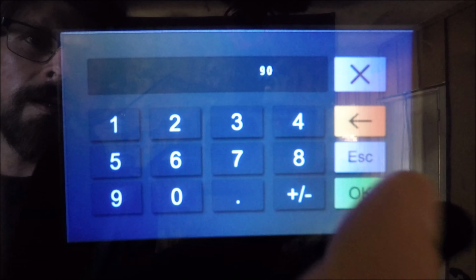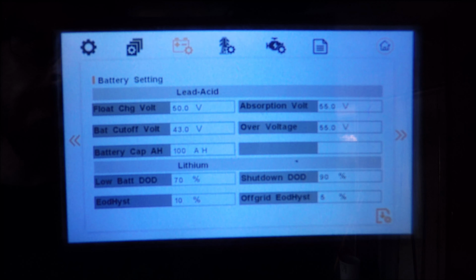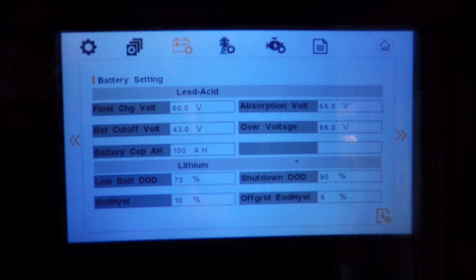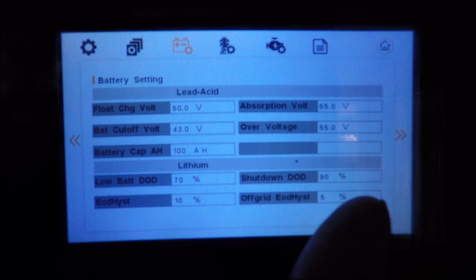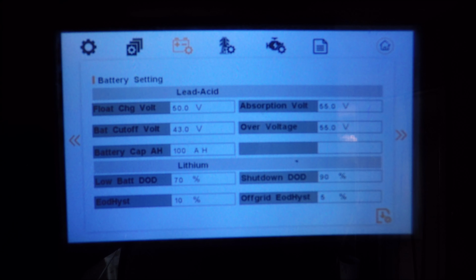What this means is once it has discharged 90% and there's only 10% left in the battery, then the inverter will shut down all of the loads. We have a 5% hysteresis here, so that means that it will have to charge up to 15%, so at least 15% of battery life before the shutdown can be overridden.